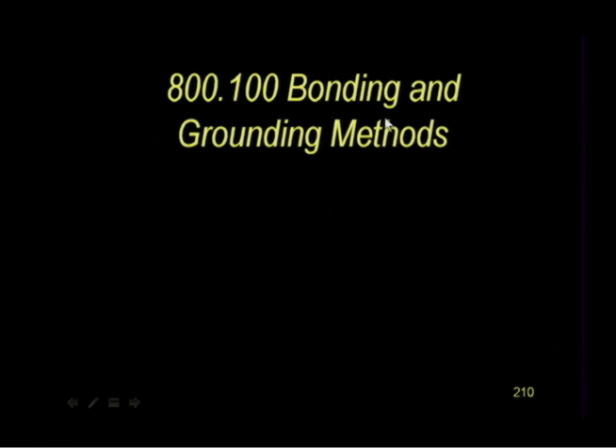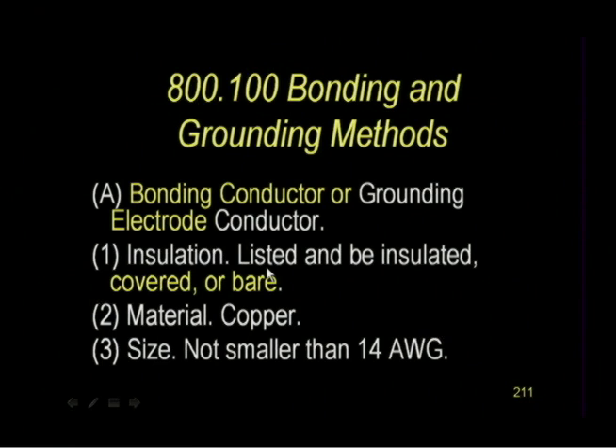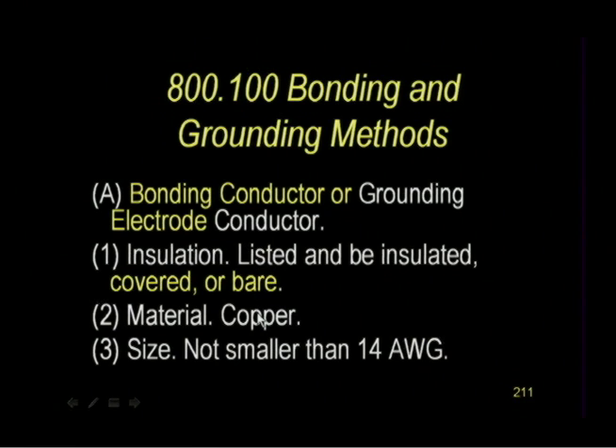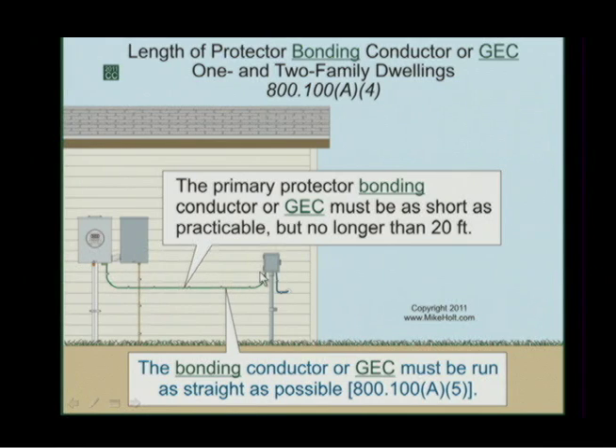Bonding methods — not grounding methods, bonding methods. Bonding conductors must be listed. They can be insulated, covered, or bare. Bonding conductors are copper. Bonding conductors are not smaller than 14 AWG. So the key: this bonding conductor is copper, not smaller than 14 AWG, and it can be insulated or bare. No color required.